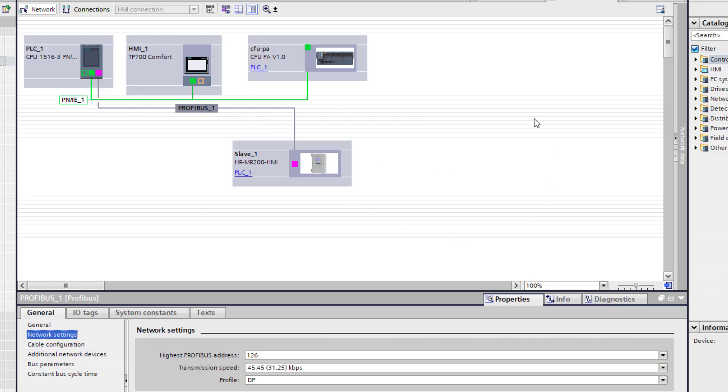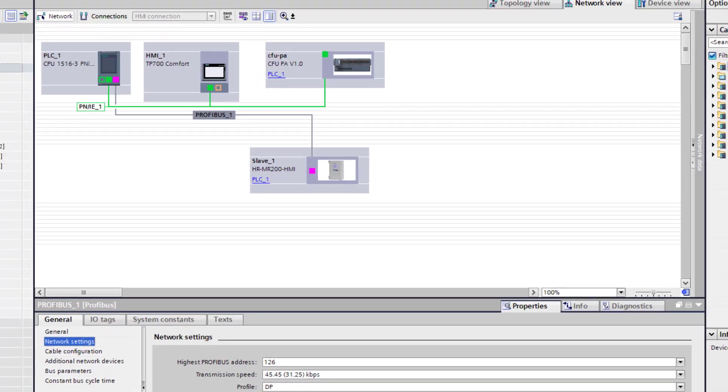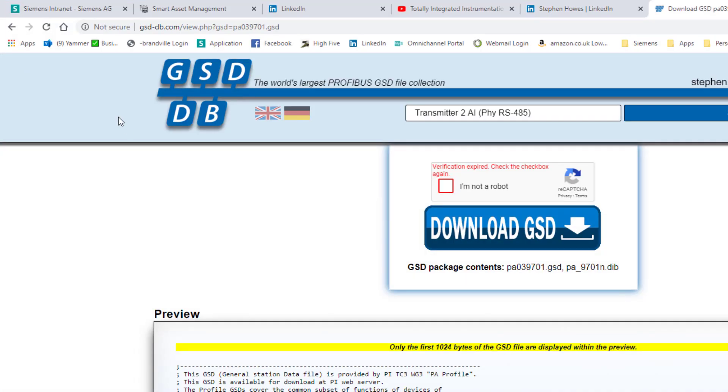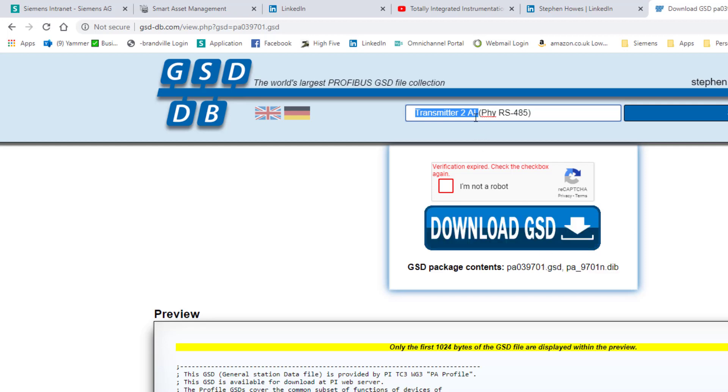So just be careful overloading your network with too many devices on one DP card. You can add extra DP cards to help. The first thing we need to do is slow the bus speed down, and then the next thing we need to do is install the GSDs. You can get the manufacturer's GSD, but what I'm going to show you here is on this website we can download the profile specific GSDs.